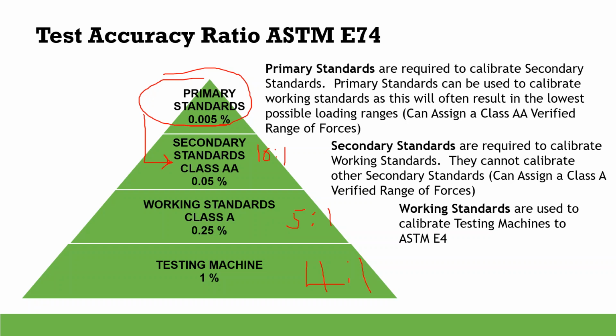So your working standard has to be 4 times better than your testing machine. Then the standard used to calibrate that working standard needs to be 5 times better. And then the primary standards need to be at least 10 times better than the secondary standards. Really, when it's confined, it works, and that's why you have to propagate correctly. So if somebody has a secondary standard with a Class AA and tries to calibrate another instrument and assign it, it doesn't work. Now we're not maintaining any type of test accuracy. In fact, we're propagating error that can be quite large as we soon approach one-to-one status, which is not good.